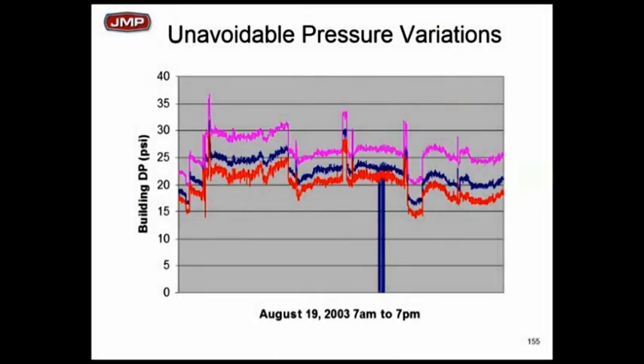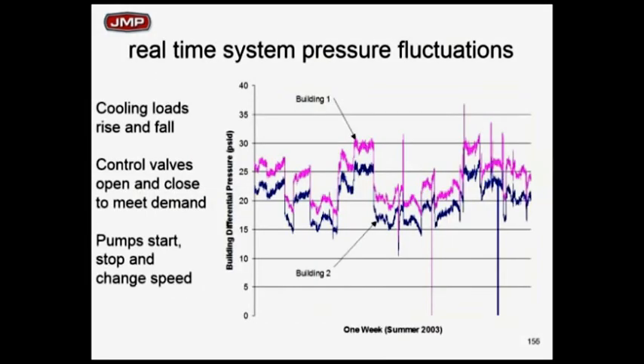Here's the reason. You're getting unavoidable pressure variations in a system. Differential pressures across the two-way valves are jumping up and down in great big systems. Not by huge numbers, but 5 or 10 pounds. And they're changing instantaneously. Valves open and close, you turn pumps on and off, somebody's changing T-stats. There are always these differential pressure fluctuations. What does that do to you?